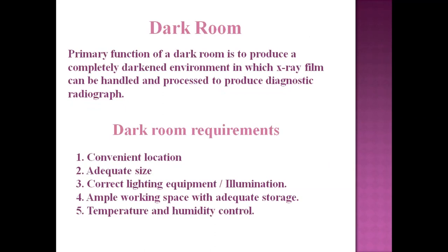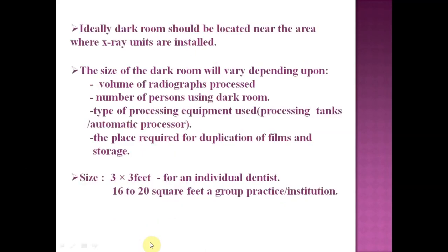Regarding the dark room — this is the area where x-ray film processing takes place. The primary function is to produce a completely darkened environment in which x-ray film can be handled and processed to produce a diagnostic radiograph. Requirements include convenient location, adequate size, and adequate illumination, ample working space, and temperature and humidity control. Ideally the dark room should be located near the x-ray units. Size varies depending on volume of radiographs processed, number of persons using the room, and type of processing equipment.